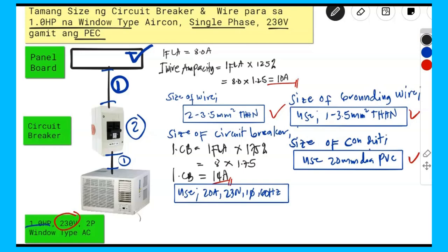To summarize our calculation, ang size of wire na ginamit natin na dapat pwedeng gamitin is dalawang 3.5 square mm na THN, at saka yung size ng grounding wire is isang 3.5 square mm na THN, at saka yung size ng conduit is 20 mm diameter na PVC. Then yung circuit breaker is dapat 20 amperes, 230 volts, single phase at 60 hertz. So ganito lang mag-size or tamang size ng circuit breaker and wire para sa isang 1.0 HP or 1 HP na window type aircon, single phase, 230 volts.